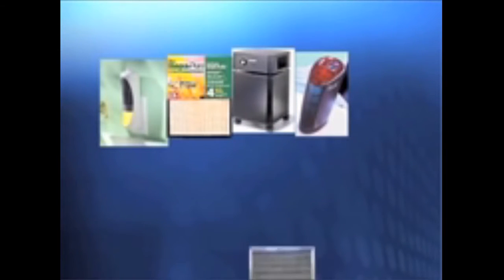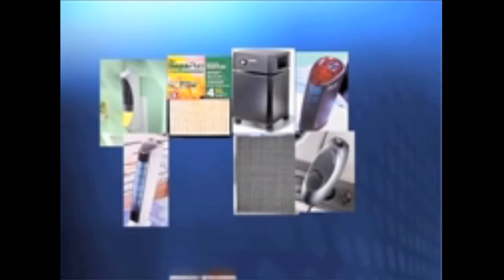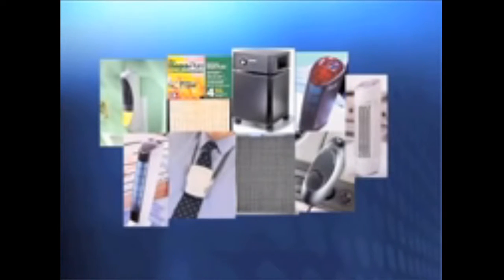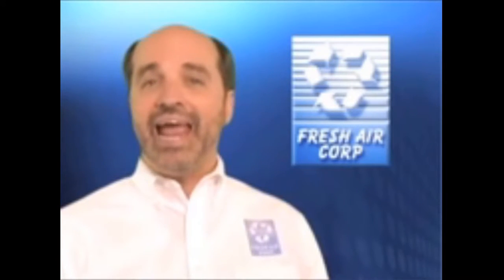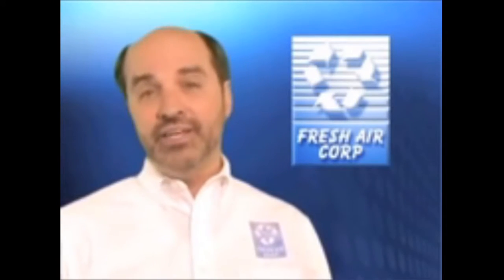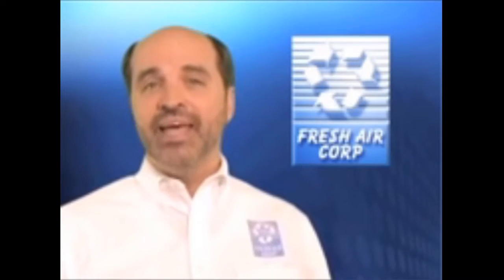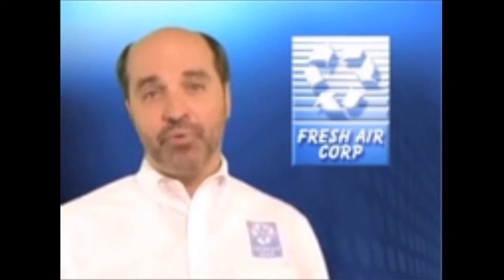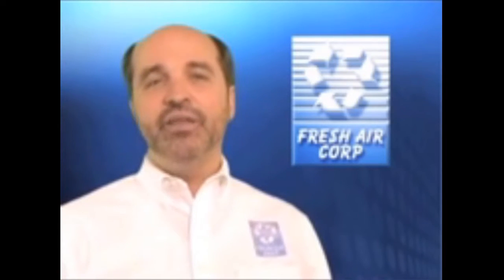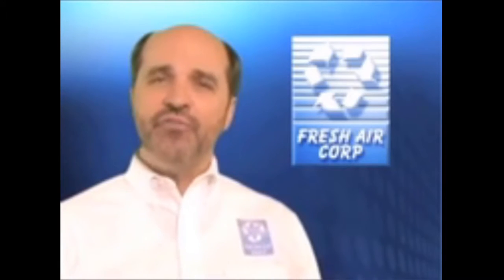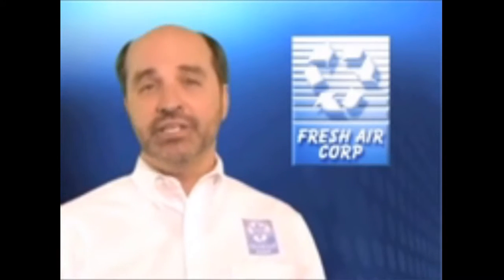If you're concerned about the quality of air in your home, you've probably noticed the advertisements for room air purifiers, special furnace filters, plug-in air fresheners, and disinfectant sprays that promise to clean up your indoor air. Now, while these products may have merit for a specific area, like the bathroom, or a strong cooking odor, most of them miss the real point. They're addressing the symptom, not the problem. The reason the air in many homes is so dirty is often because the ventilation system is contaminated.